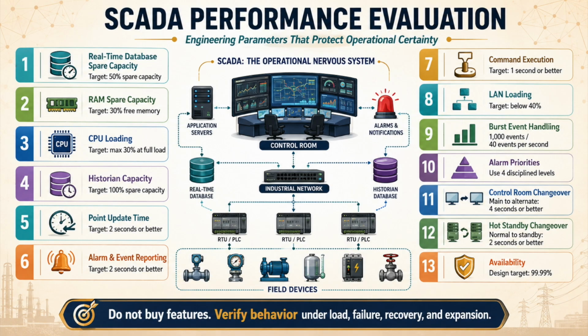The second engineering parameter is RAM spare capacity, because memory pressure does not always create dramatic failure. It creates slow graphics, delayed alarm loading, sluggish trends, failed reports, paging dependency, unstable client behavior, inconsistent primary and standby performance, and intermittent faults that are difficult to diagnose, especially when virtualization introduces memory oversubscription or mixed server roles.